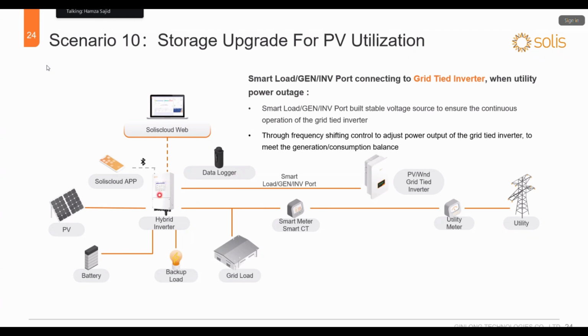There is one thing, the hybrid inverter and the on-grid inverter power should be the same. If it is 5 kilowatt, it should be 5 kilowatt or less than 5 kilowatt. If it is 20 kilowatt or 30 kilowatt, the power can be from 5 kilowatt to 30 kilowatt, but it should not exceed the power of the hybrid inverter.